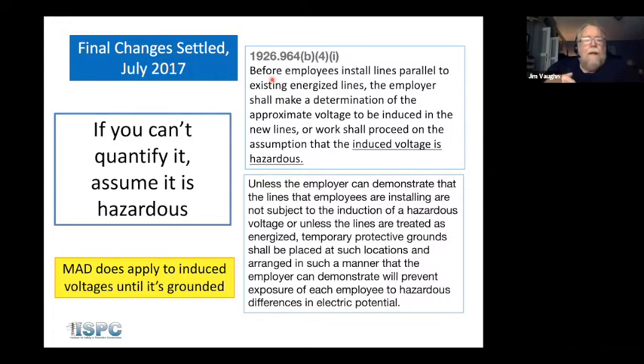Okay. All right. If you can't quantify it, you have to assume that it's hazardous. We're talking here about induction. Now, we have an issue with induction in that we have a lot of low-level induction, and linemen forever have been coming up to de-energized distribution next to a transmission circuit or to a transmission circuit, and they bump against it and they get a shock. And they go, ooh, that's bad static on here today. It's not static. This is induction. It's the same thing that makes a transformer work, and it will kill you. Static won't kill you unless it's lightning, but AC voltage will, and that's what induction is.